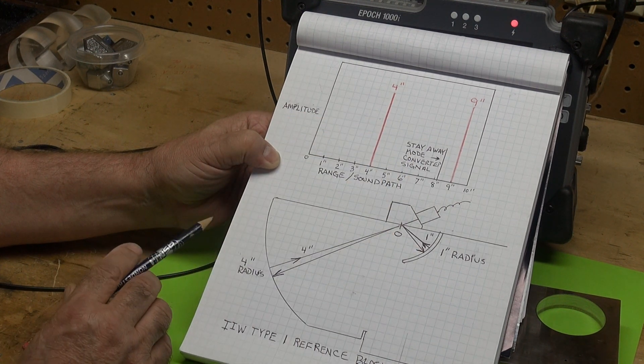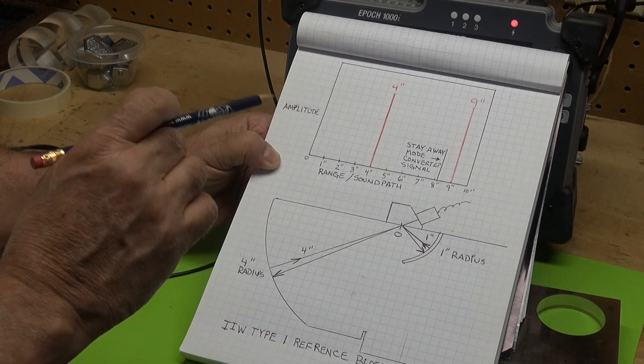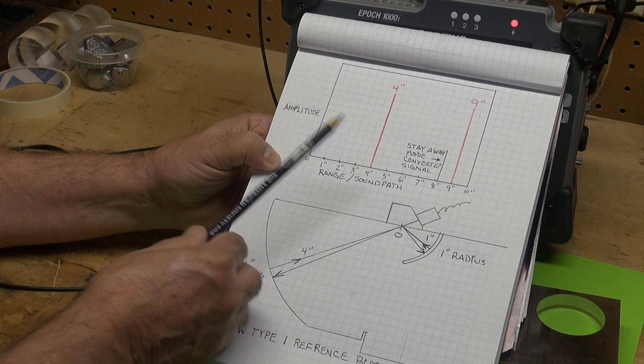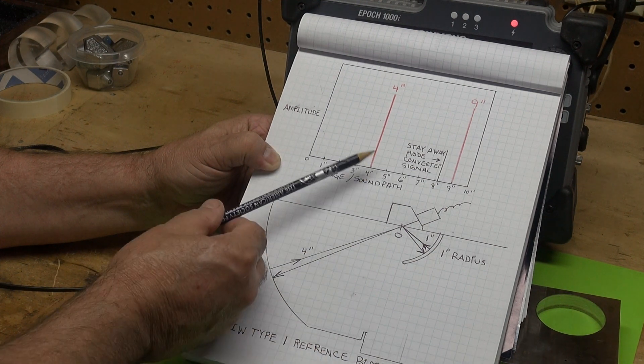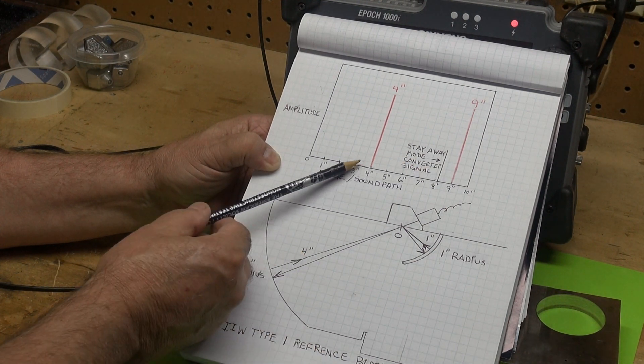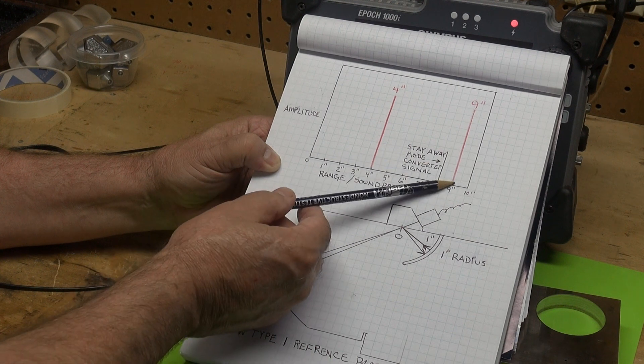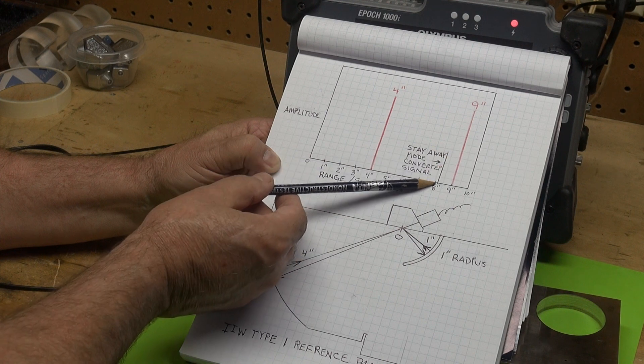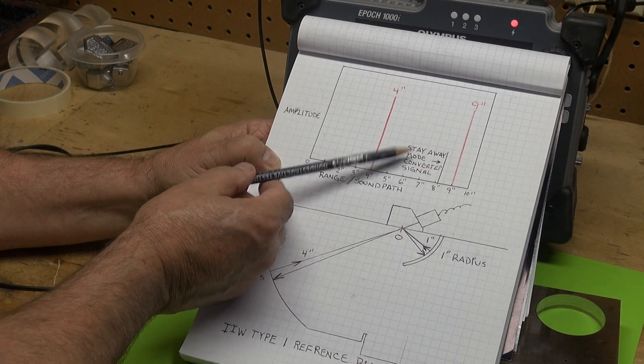That explains how this works. Now there's one caution I want to talk about. When you calibrate, set your range at 10 inches. Depending on the transducer, you'll definitely see the 4 and 9 inch radiuses, but you may see a signal coming up right around 8 inches or so.